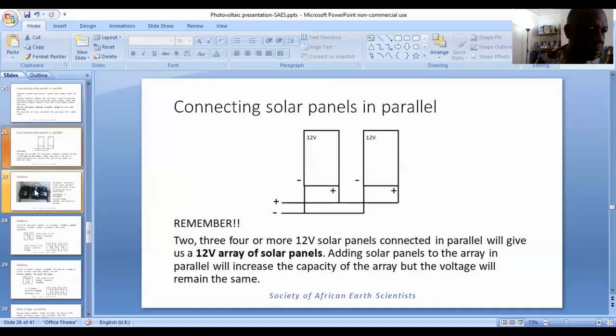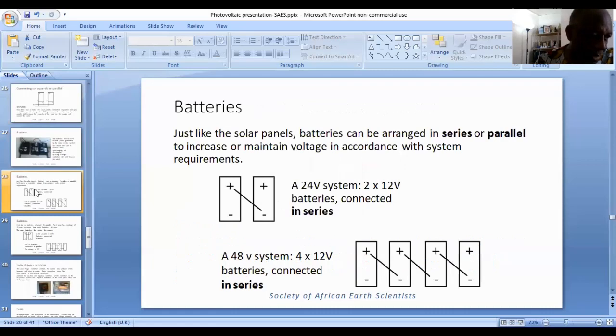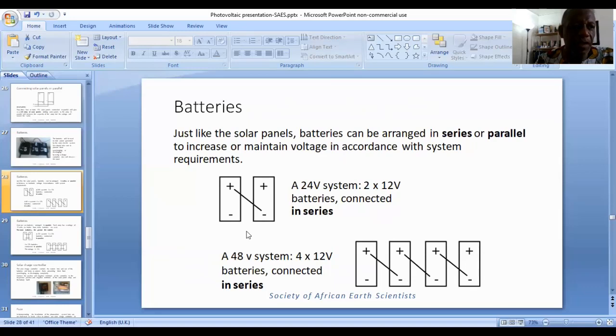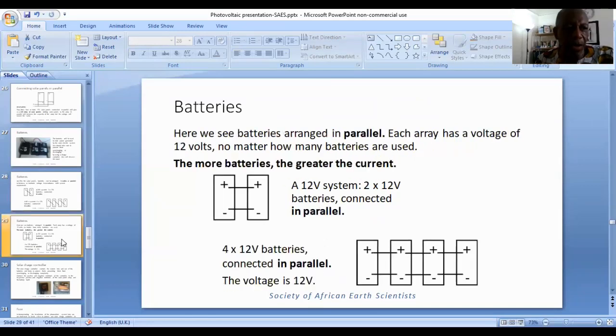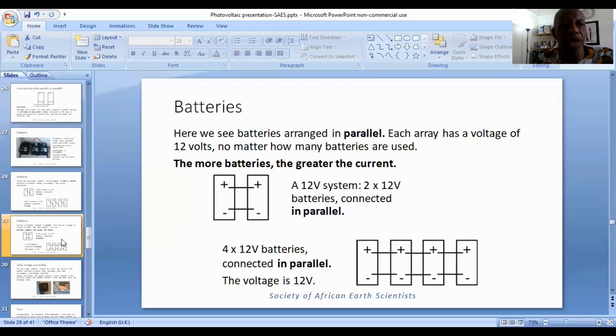Batteries follow the exact same procedure. Two 12-volt batteries in series will give a 24-volt battery array. Four 12-volt batteries in series — that is positive to negative, positive to negative, positive to negative connections — will give a 48-volt system. When we come to parallel, the parallel connections do not increase the voltage. Two batteries or four batteries connected in parallel — that is positive to positive, negative to negative — will give you a 12-volt array.